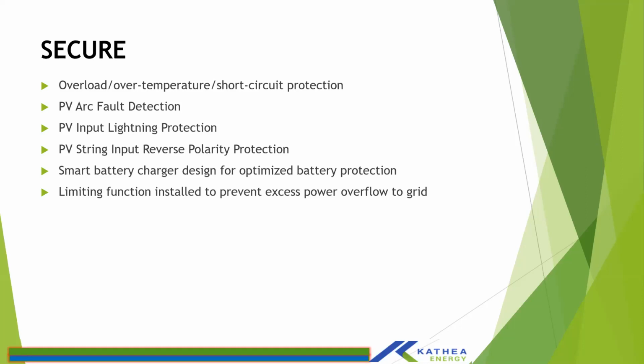And then for the lithium batteries, if you connect your cable, the system will automatically pick up the battery and all the battery protection readings from the BMS, that is the charging current, floating voltages and all that. And then it will use those for optimized battery protection. However, if you are using an LG or a lead acid battery, then all those functions you would need to set manually on the battery setup. We'll look more in detail on that in our tomorrow session on commissioning.